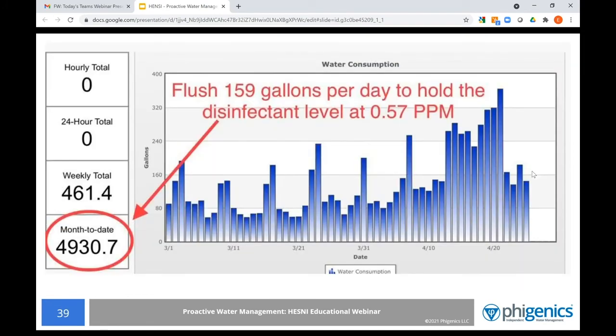And so part of this project from an efficiency standpoint was understanding how much water it took to achieve that balance between safety and efficiency. And so we were able to quantify this with a water meter that sent our data to the web. And so for this specific hot loop, it took an average of 159 gallons per day to maintain that disinfectant level. And so one thing that's really important to note is that this is not a straight line graph.